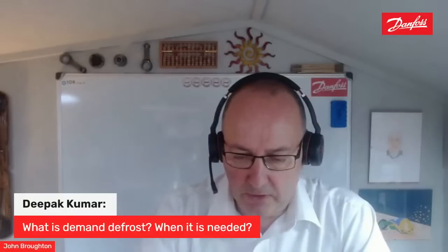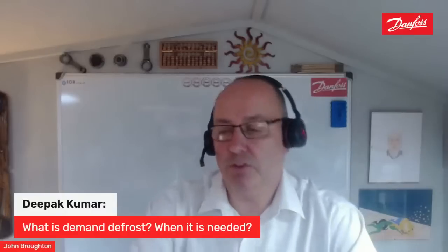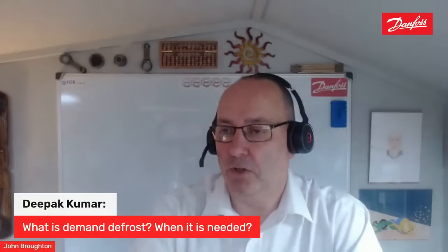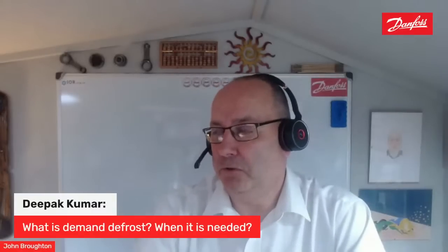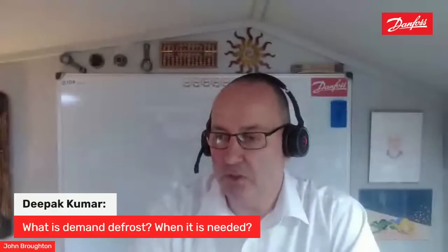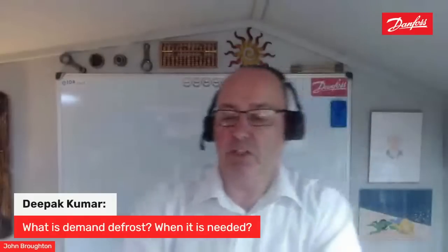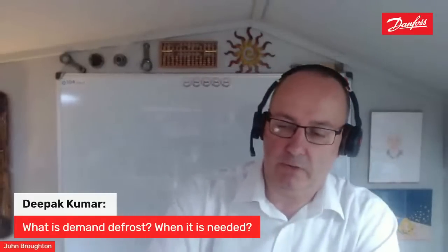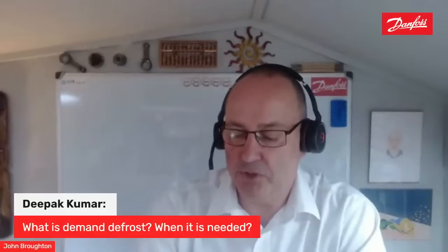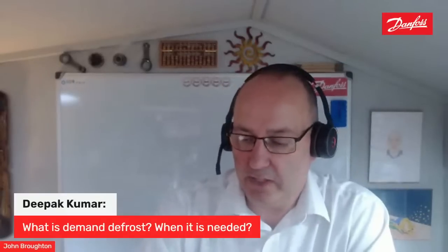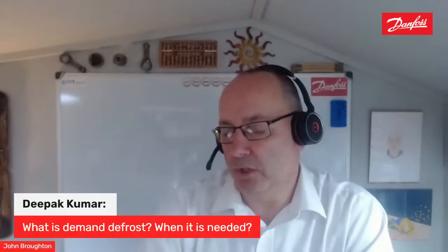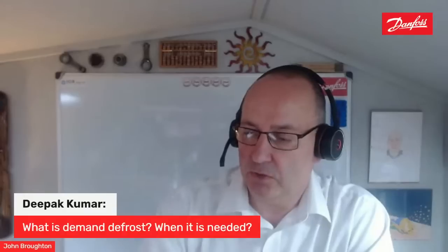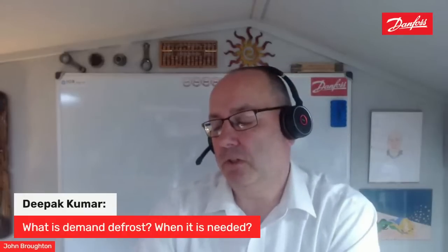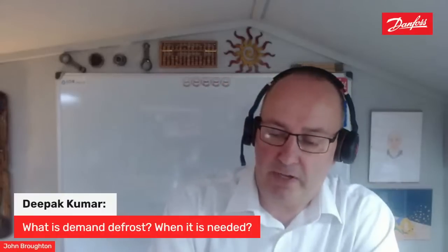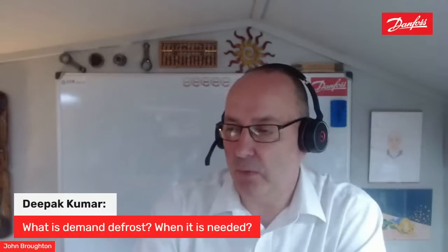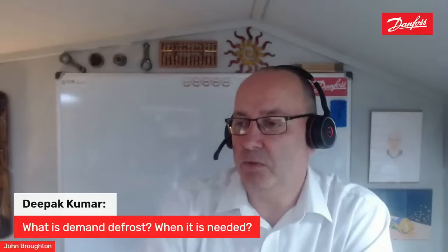You can have, on let's say a Danfoss evaporator controller, Danfoss case controller, a functionality called defrost on demand. That controller will look at that evaporator. It'll look at the air on temperature, air off temperature, the amount of refrigerant that's going through, the length of defrost times, etc., and it will calculate, does it need to do a defrost this time or can it skip this defrost? And if it is set up correctly, then it works very well, but it has to be set up and it has to be commissioned.